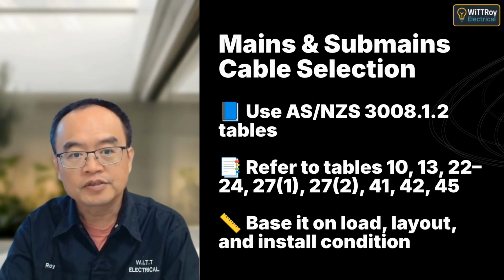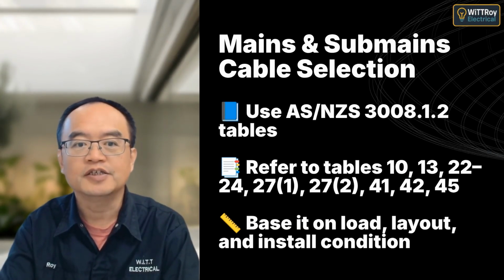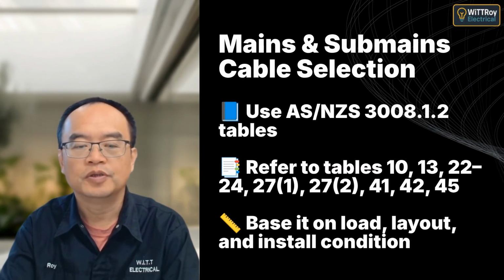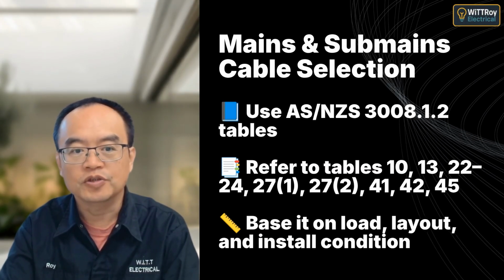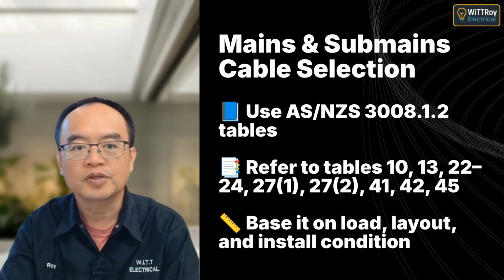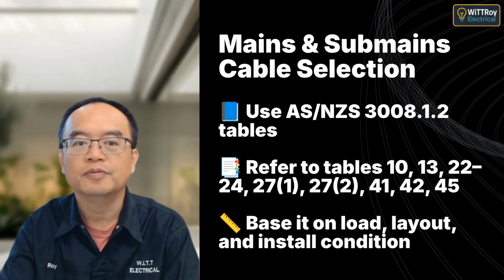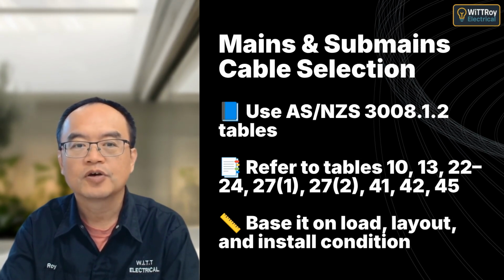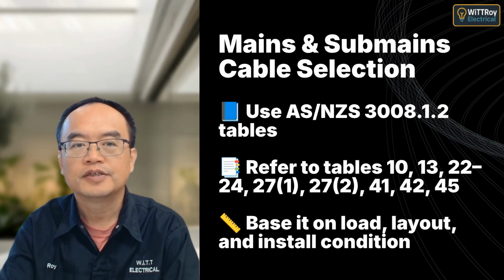When selecting mains and submains, refer to AS/NZS 3008.1.2. Tables like 13 and 24 help choose cable size based on current carrying capacity, ambient temperature, and installation type. Correct selection avoids overheating and meets safety standards.